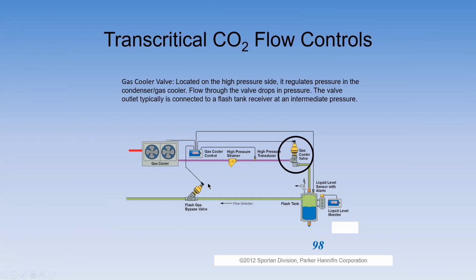Between this valve here and this valve here, I'm playing games with the environment inside the flash tank. So if that CO2 has gone past the critical point and become transcritical, now I can get it below the critical point and get all of the CO2 back to 100% liquid, with as much subcooling as I can get out of it.